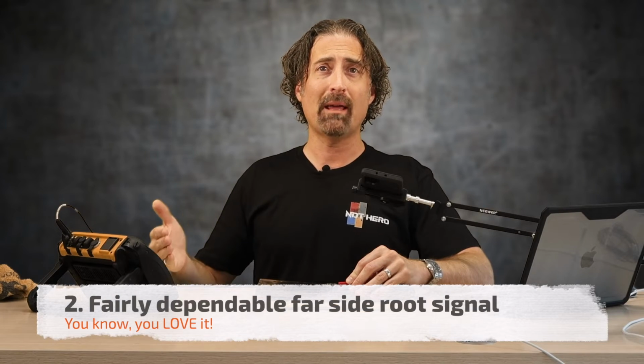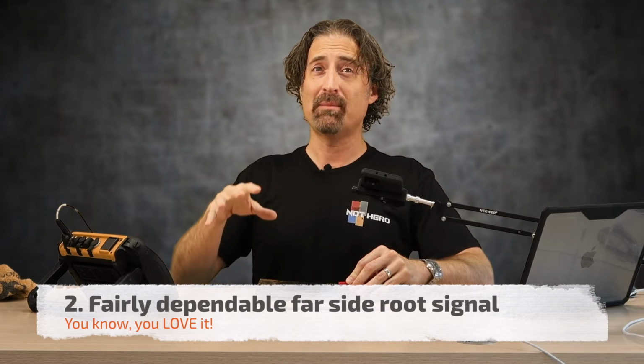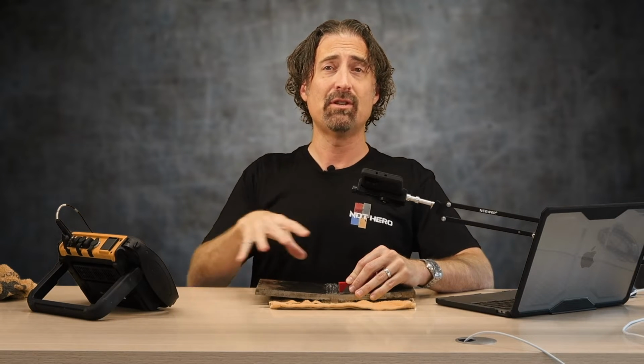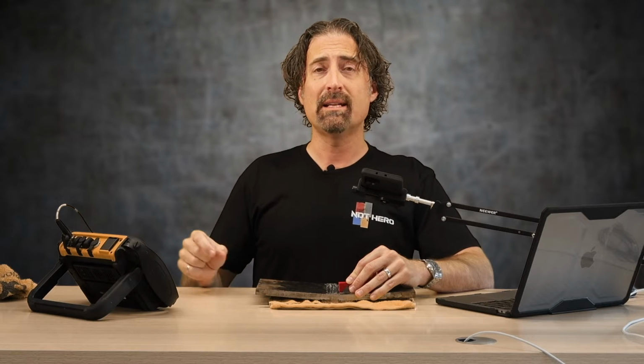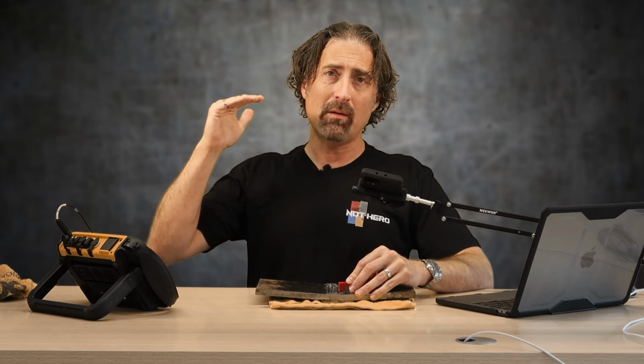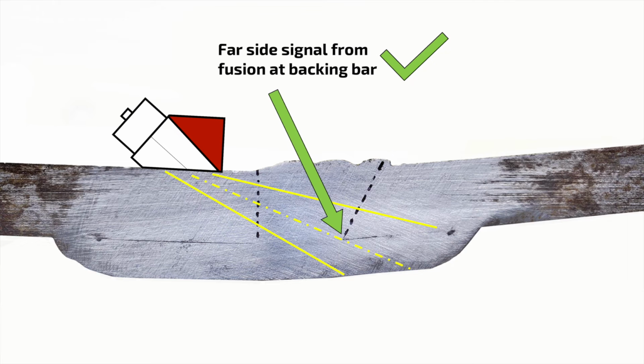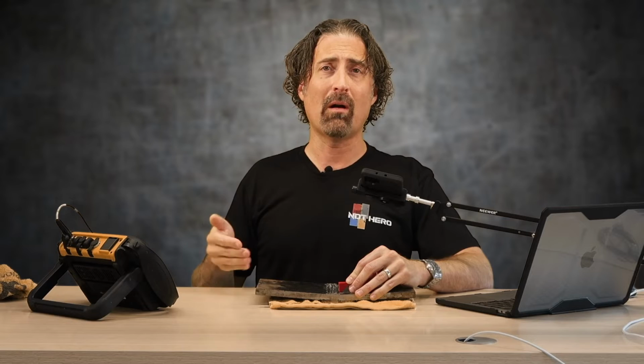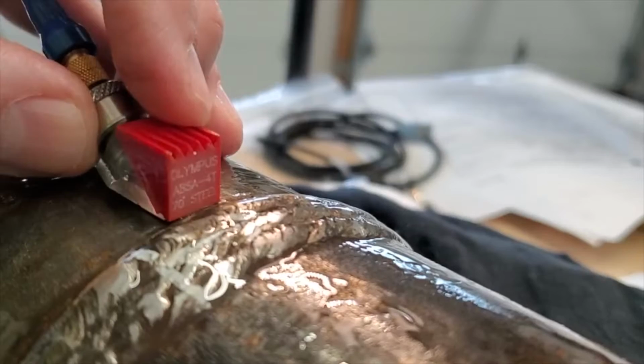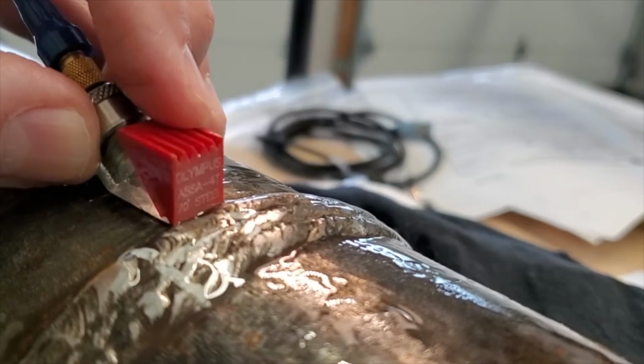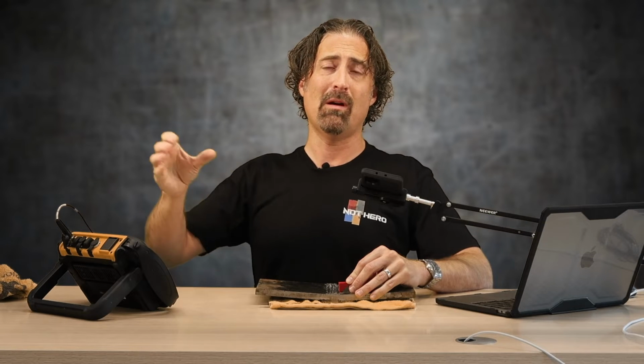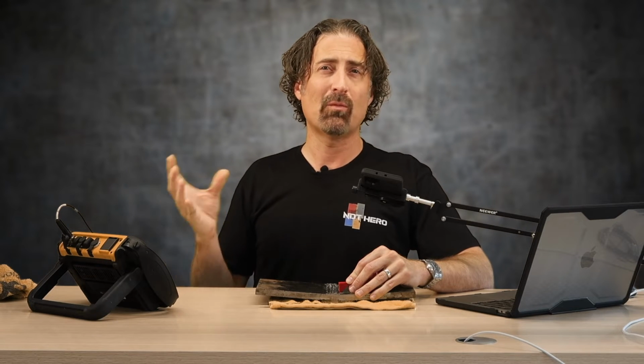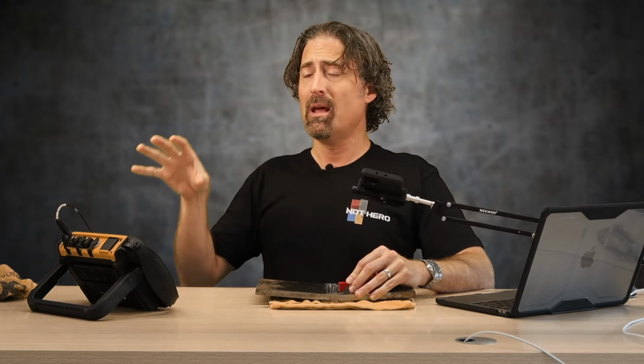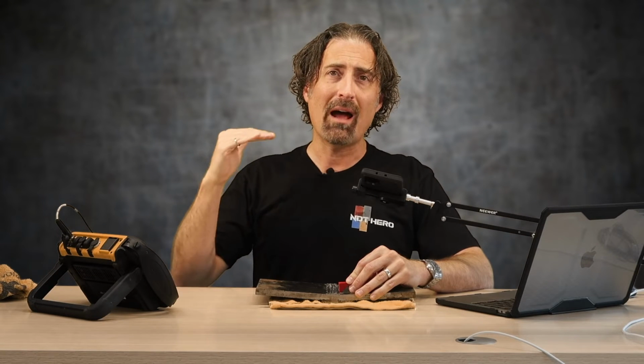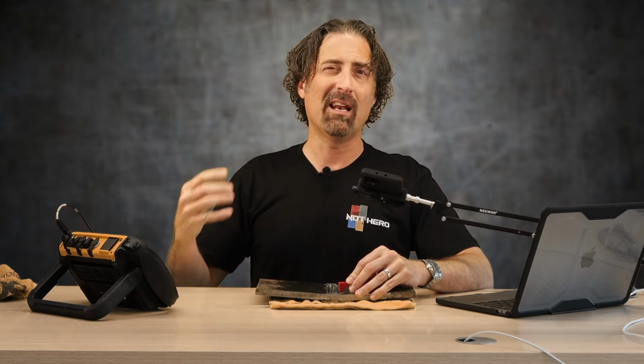The second thing about backing bar welds, and I actually think this makes them easier to do, or at least easier to position your transducer and know where you are, is the fact that when the weld fuses to that backing bar, on the far side of the root, you do get a nice reflector. So you can tell immediately where you are. You may not get this on a piping weld because the amount of penetration that you get on the bottom and the amount of root cap is not really going to be that consistent on the piping weld. But when you have the backing bar, you do have that one location where you should get a little bit of sound off of it.